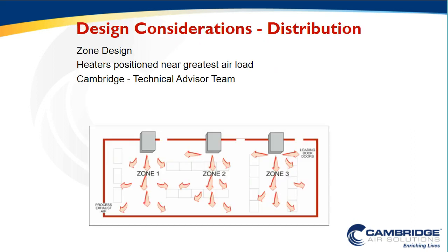Now, not every warehouse, not every distribution center is going to be the same. So we must think about how the building is being used, where our operable doors are, how they are utilizing the rack systems, how dense they are, and how the racks or the storage product are laid out in reference to our heaters. So obviously we must take into consideration how the building is being used and how it's being set up in order to get good temperature distribution. But by utilizing some of the key design teams available to you, these systems can be deployed to meet that 2 to 5 degrees temperature variation wall to wall, floor to ceiling, without adding additional air movement devices.